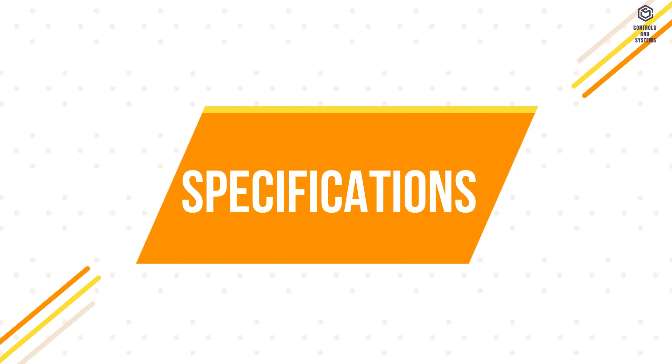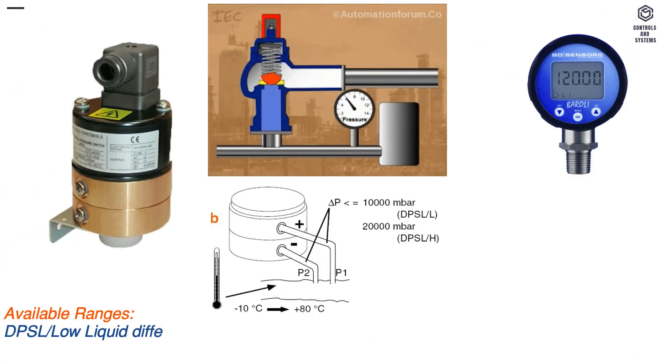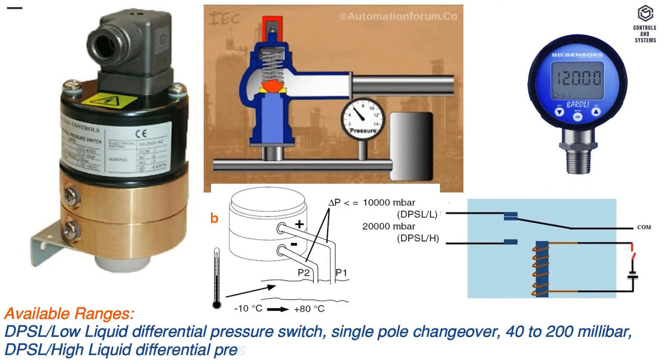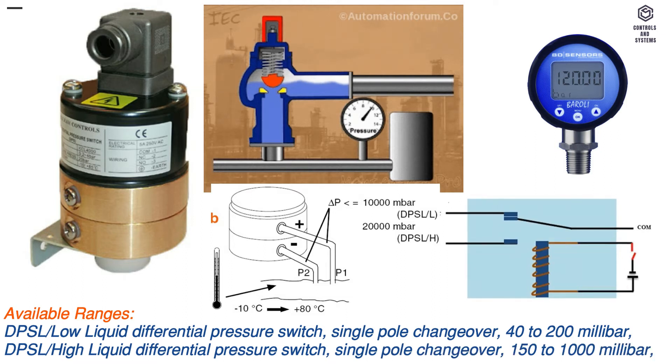Specifications. Available ranges: DPSL, low liquid differential pressure switch, single pole changeover, 40 to 200 millibar. DPSL high, 150 to 1000 millibar.